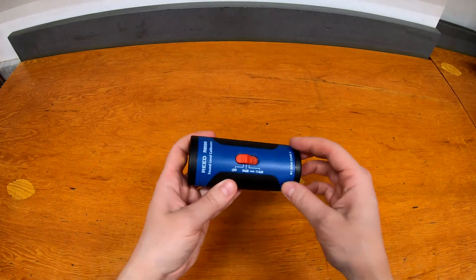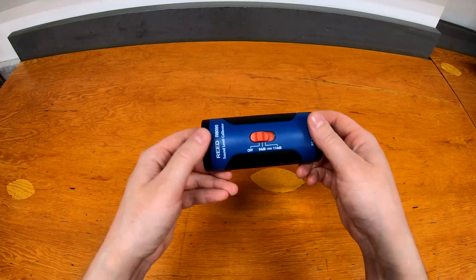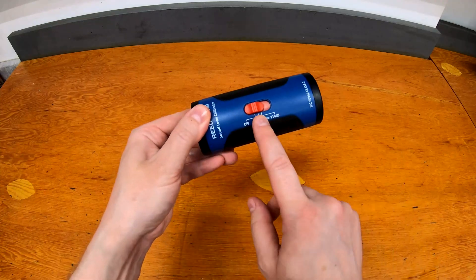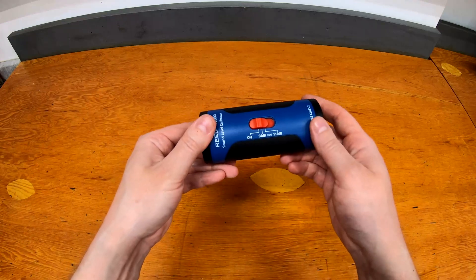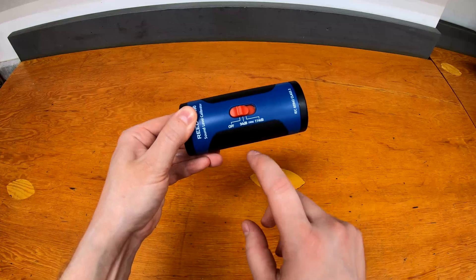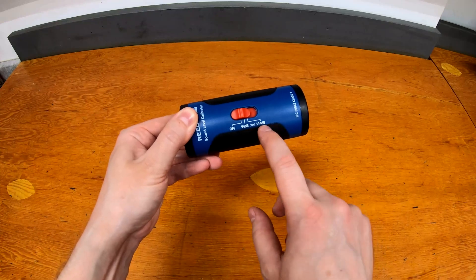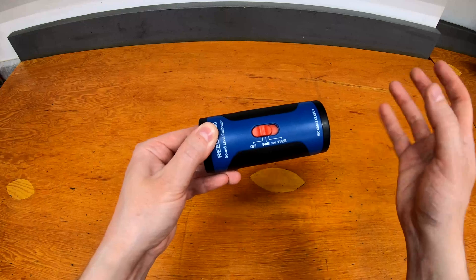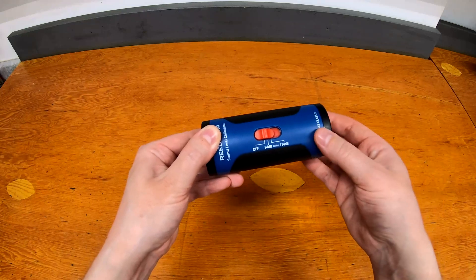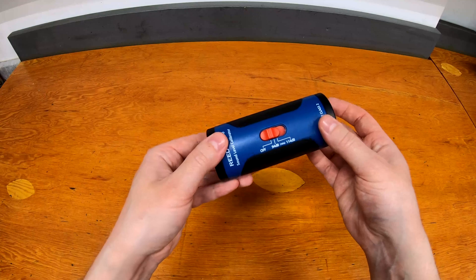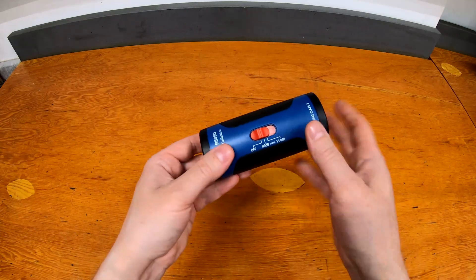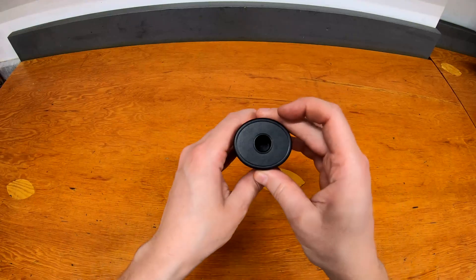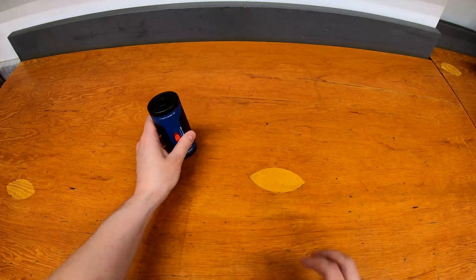It's very simple how it works. The interface is as simple as it comes. You put a battery in the back and there's a slide switch: off, 94 dB, and 114 dB. What that means is it produces a test tone at one kilohertz at either 94 decibels or 114 decibels. Then you can use the calibration screw or the level on your input for your measurement microphone to set it to these specific dB readings and know that you're calibrated to that setting. The measurement mic goes in the end here, so let me show you how that works.